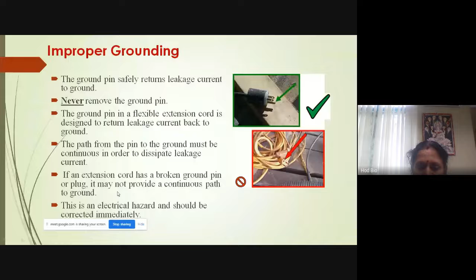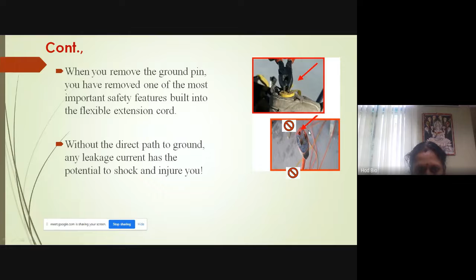The flexible extension cord is designed to return leakage current back to the ground, which dissipates the leakage current. If an extension cord has a broken ground pin or plug, it may not provide a continuous path to ground. In that case, you should correct it immediately. When you find that the pin is not properly available, or it is open, or it is removed, you can remove the plug and replace it. When you remove the ground pin, you have removed one of the most important safety features built into the flexible extension cord. So don't remove this ground pin.